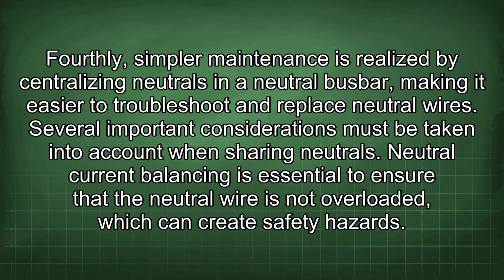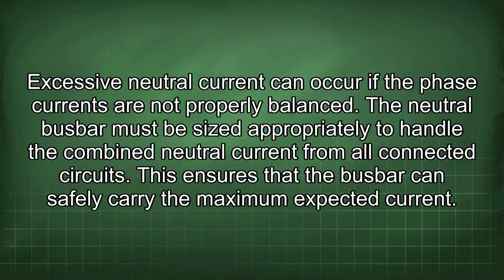Several important considerations must be taken into account when sharing neutrals. Neutral current balancing is essential to ensure that the neutral wire is not overloaded, which can create safety hazards. Excessive neutral current can occur if the phase currents are not properly balanced. The neutral busbar must be sized appropriately to handle the combined neutral current from all connected circuits. This ensures that the busbar can safely carry the maximum expected current.